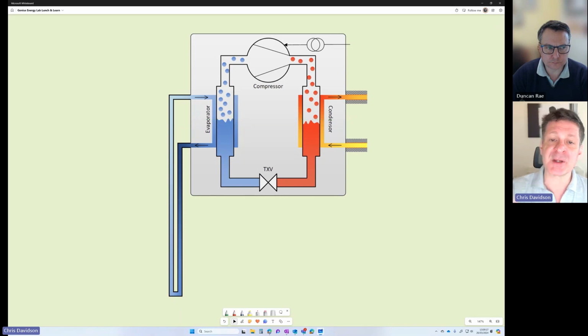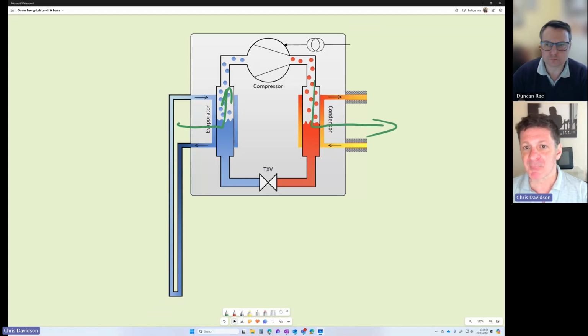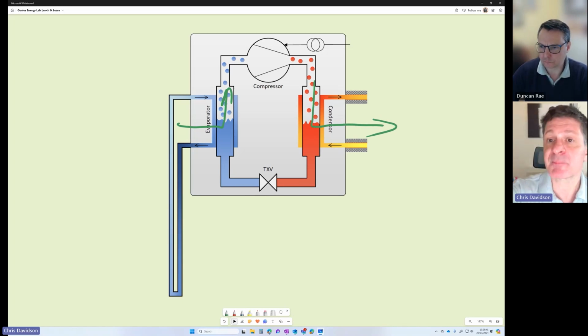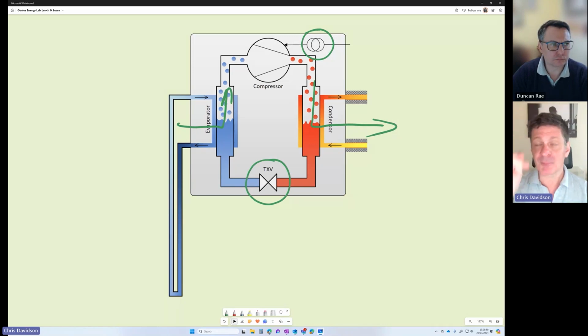It actually does that by manipulating the pressure in a liquid gas circuit, which allows that liquid to evaporate, turn into a gas, and therefore pick up energy at a cold temperature and low pressure. It can then drop that heat by condensing that gas and releasing it at a higher temperature under a higher pressure regime. It manipulates that pressure using a compressor, which is electrically driven. And there's a final part of the process, the thermal expansion valve down at the bottom here. You can think of that really as a pinhole - just like a single door in a big room, it takes people time to exit that room as a result of the constriction in the door. That's exactly what it does in a refrigeration circuit.